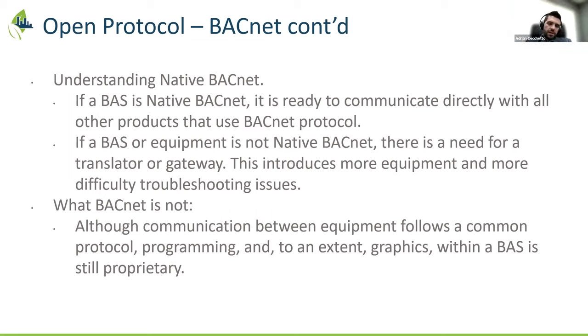Thanks, Frank. I'd say native BACnet definitely provides a much easier way to interoperate with that piece of equipment. Like you said, it's a little easier to work with out of the box. Most of the time that's because those controllers have a fully fleshed out descriptor list for all their BACnet objects, plus there's usually very good supporting documentation from those manufacturers as well.